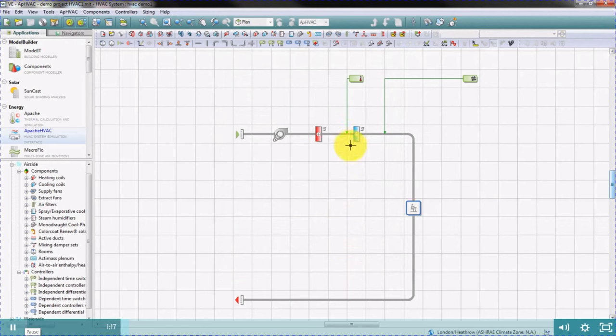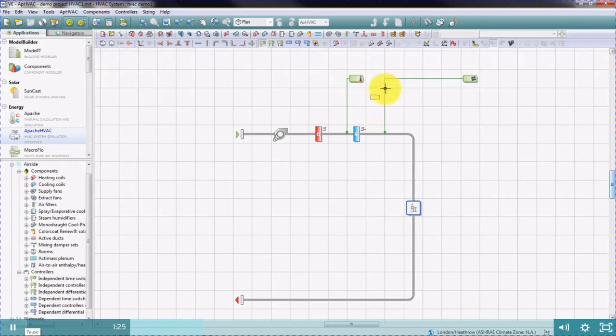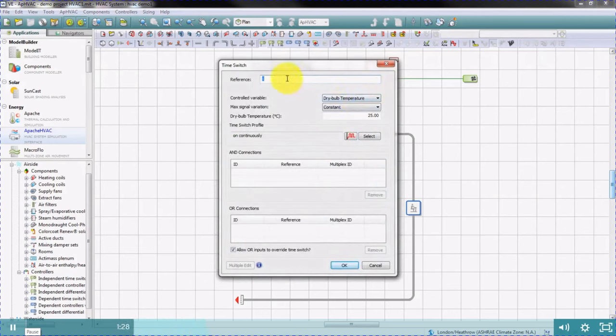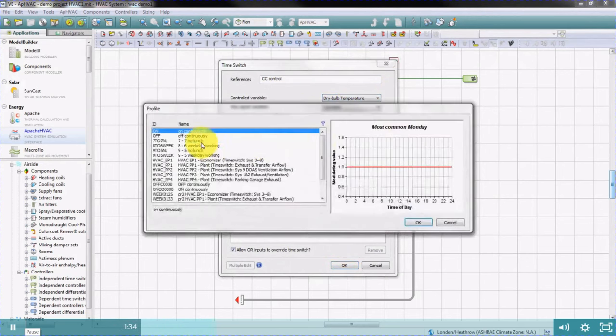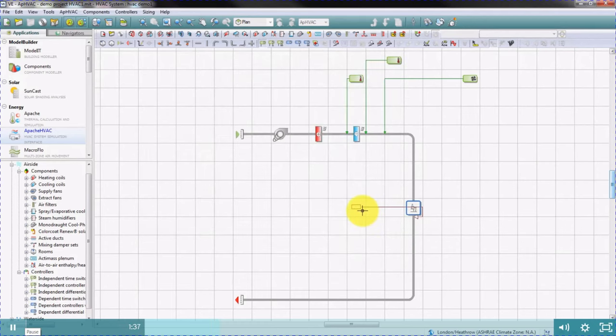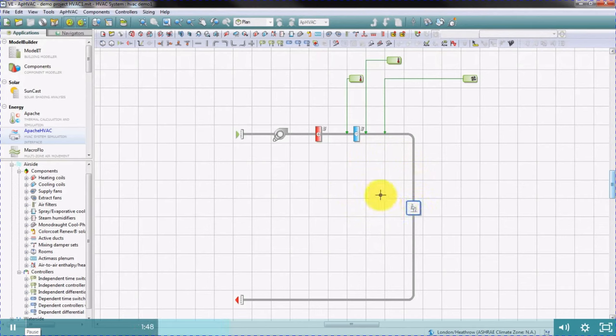In the same way, we can place a similar control downstream of the cooling coil. In our example, this means that the air is supplied into the room at between 15 and 16 degrees, as long as the coils are big enough and as long as the sources of heat and cooling supplying these coils are adequate.